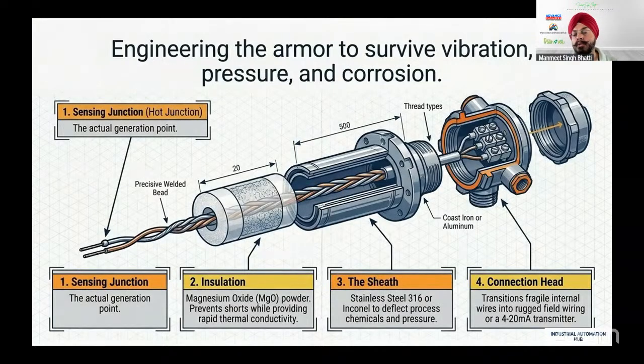Then at the end you will find the aluminum head, point number 4, which is called the connection head. So your thermocouple wires go over there and get connected. Very simple design, not a complicated design, but this is the actual engineering. So with the thermocouple, we have got a temperature sensor which is actually outside in the field where it measures the temperature, and based on that you get an output. This is the way it works.